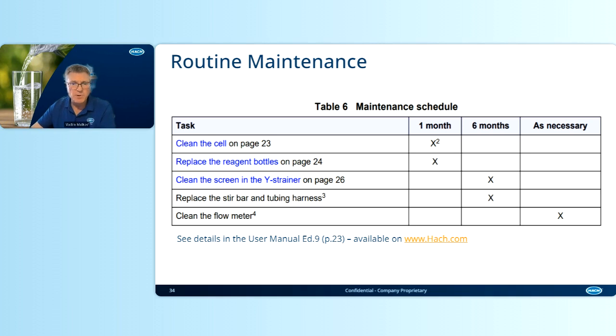Since the replacement of the bottles is also very easy, cleaning the Y strainer and the filter element in the Y strainer is, on average, recommended every 6 months for the target applications. Of course, it can be and will be more frequent for dirty water applications. And that's why we recommend adding filtration to minimize the maintenance requirements, the maintenance efforts. Now, stir bar replacement and tubing takes about 2 minutes, and for target applications, it's every 6 months.